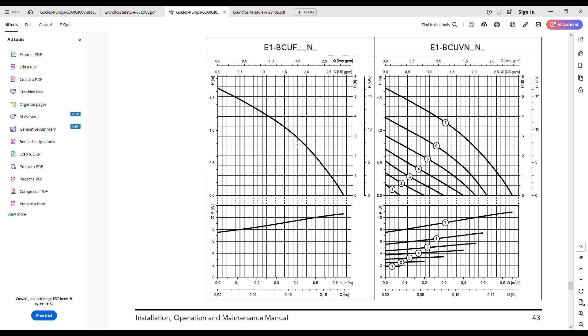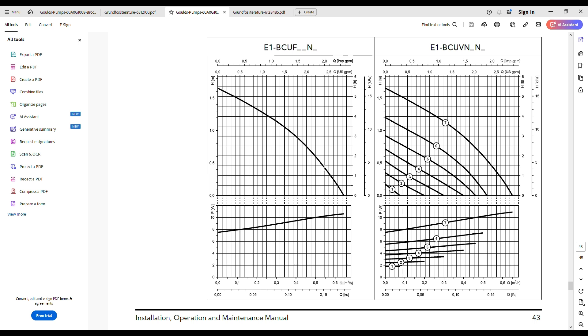So I heard this tinkling sound, so I decided to put in this valve. What I believe was happening is on any kind of pump, if you get down here, this is the pump curve. So what we have across the bottom here is the flow rate, and then this is the pressure or the outlet head as they call it. What I believe was happening with mine was I was close to or beyond the maximum because everything was wide open. There was no restriction on the outlet.